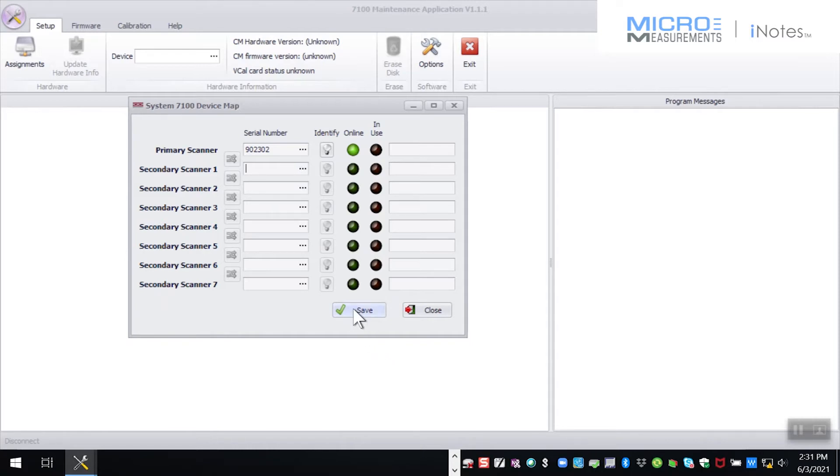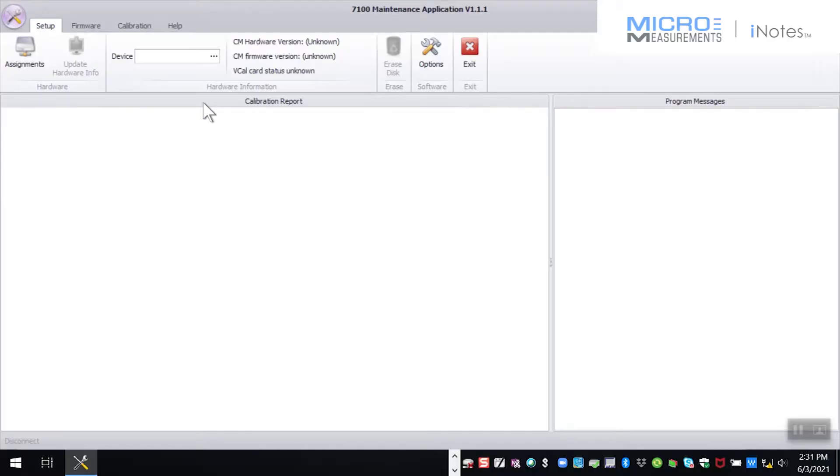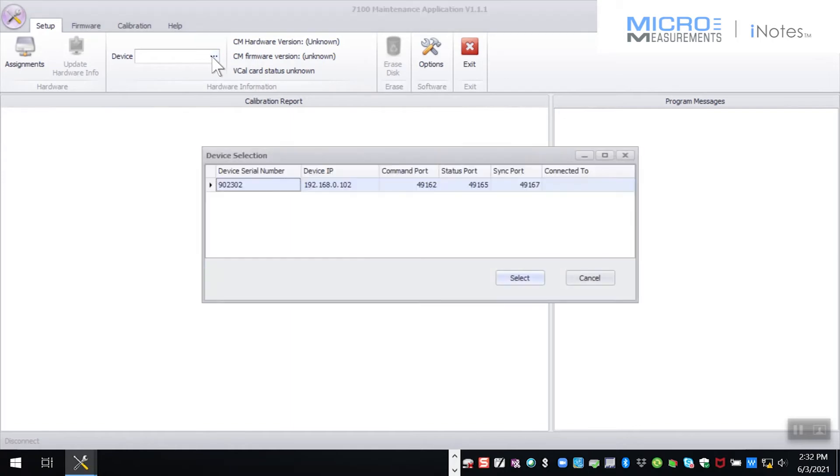And basically we're done. The only thing that we had to do with the maintenance utility has been completed. I can close this out now and I can fire up my strain smart software and go have fun taking data. But a word of caution, legal disclaimer and all, don't run both at the same time. Please do not run this maintenance utility and strain smart at the same time. Close one of them out or both of them out because they will conflict with each other trying to control the scanner. But instead of doing that we're going to show you the other aspects of the maintenance utility.